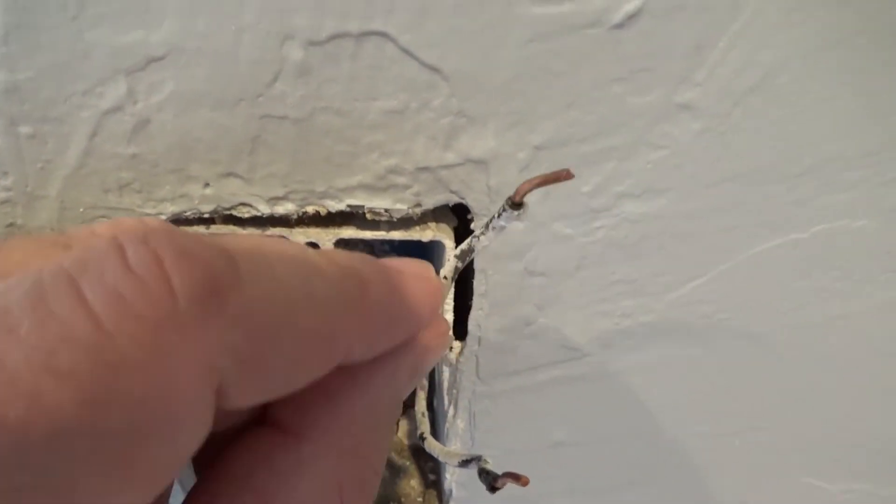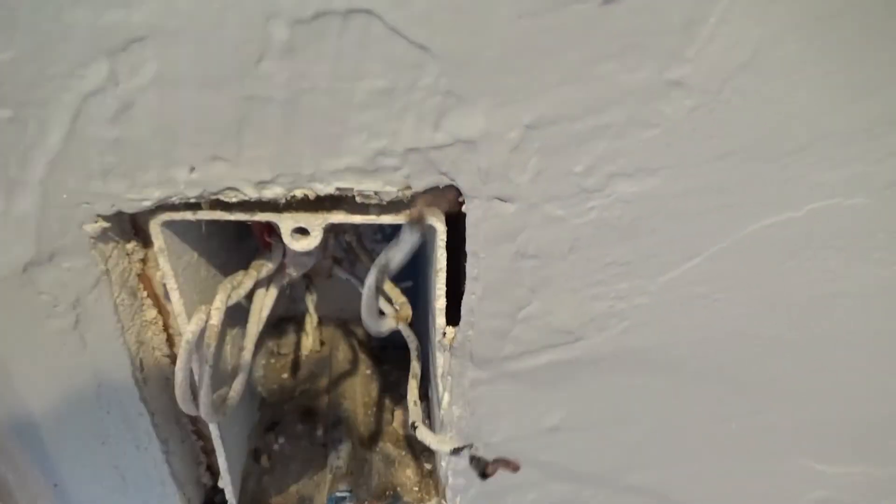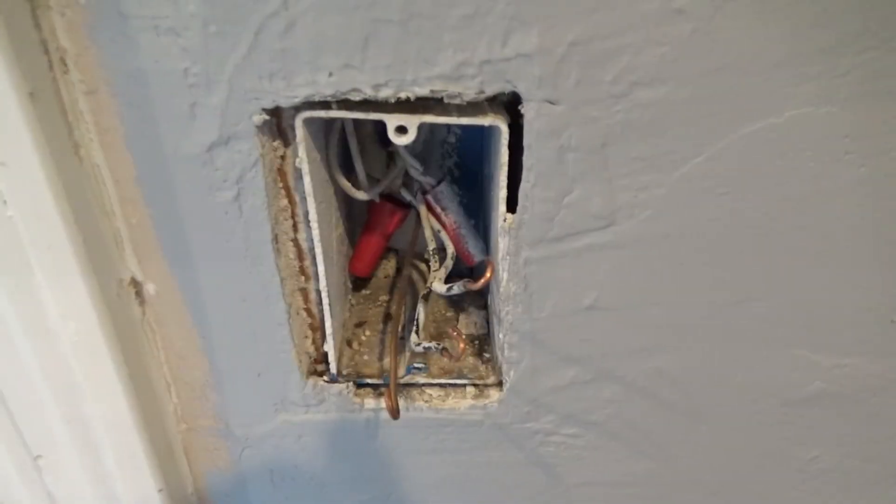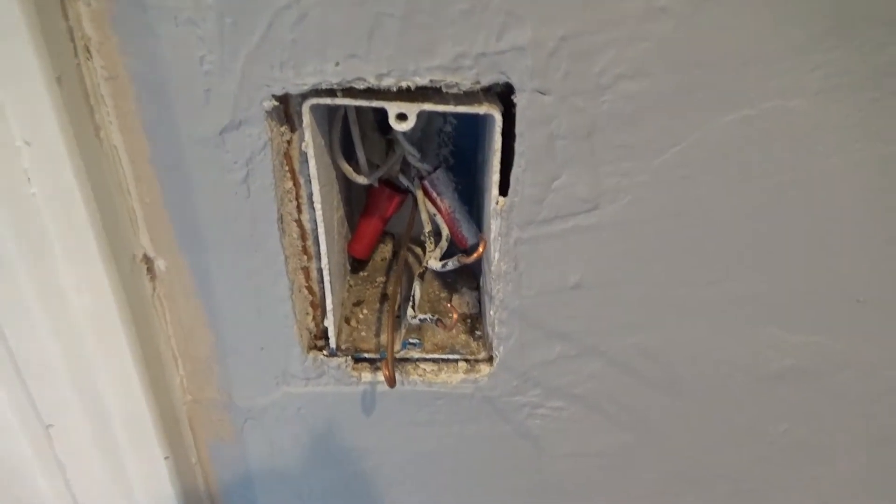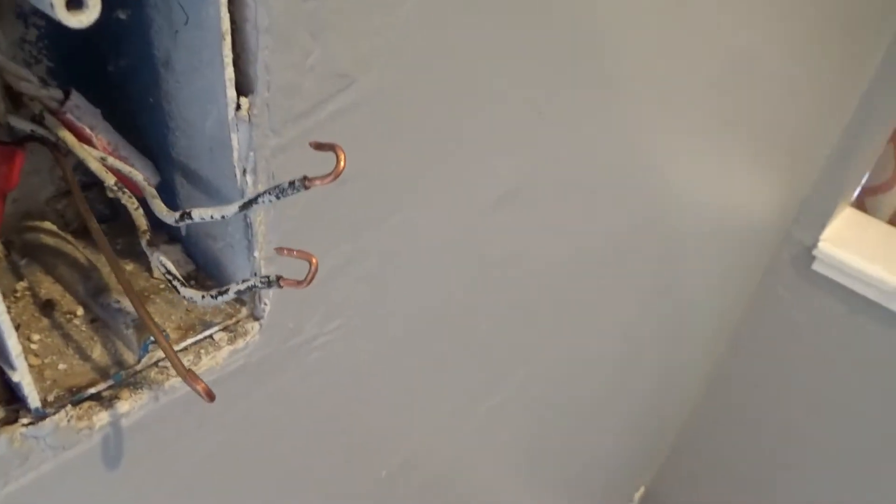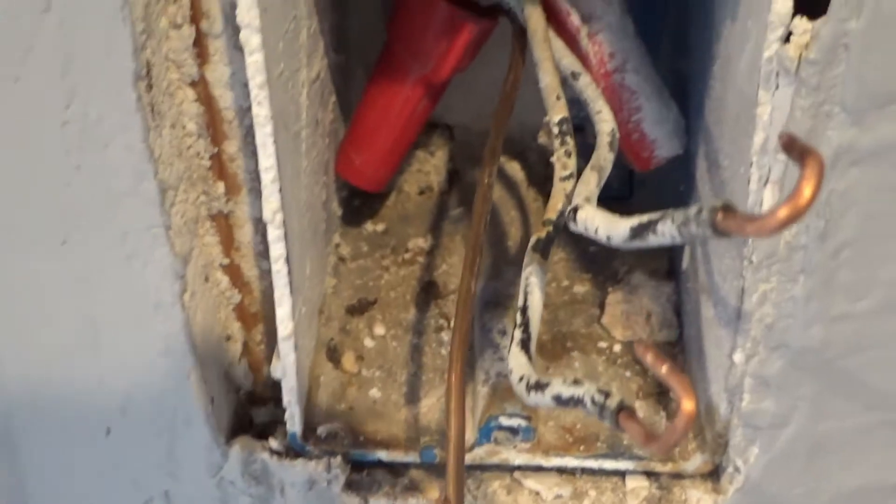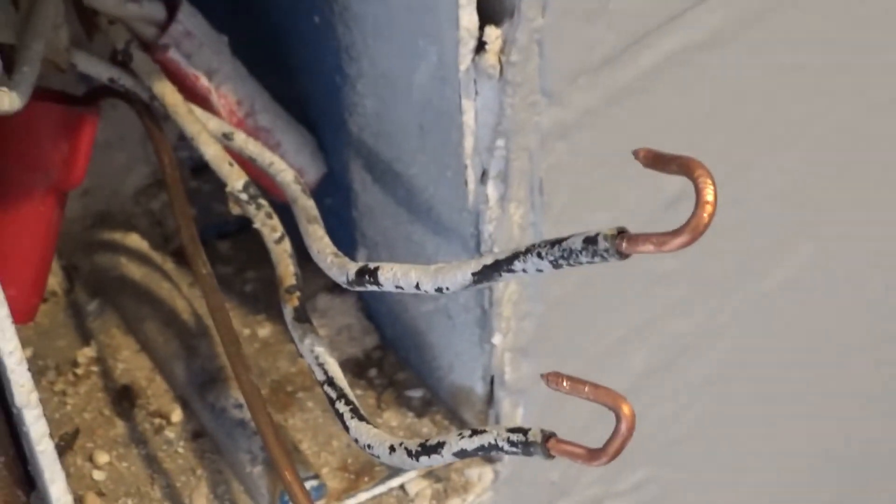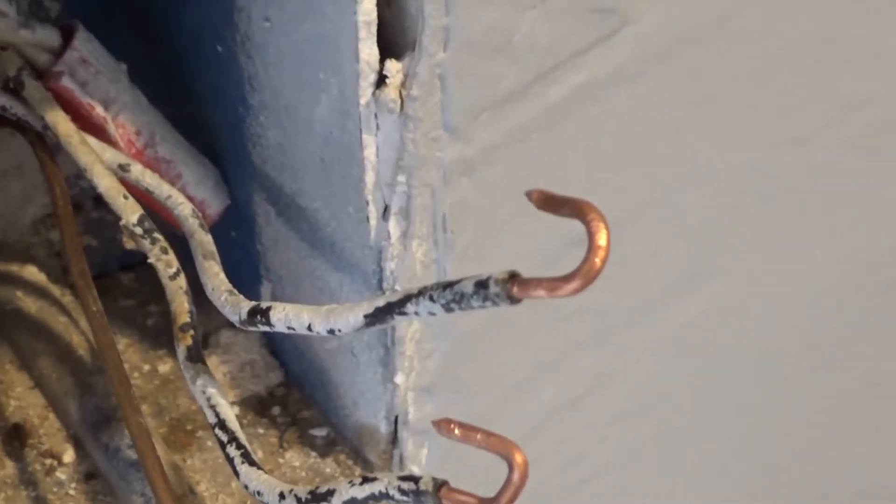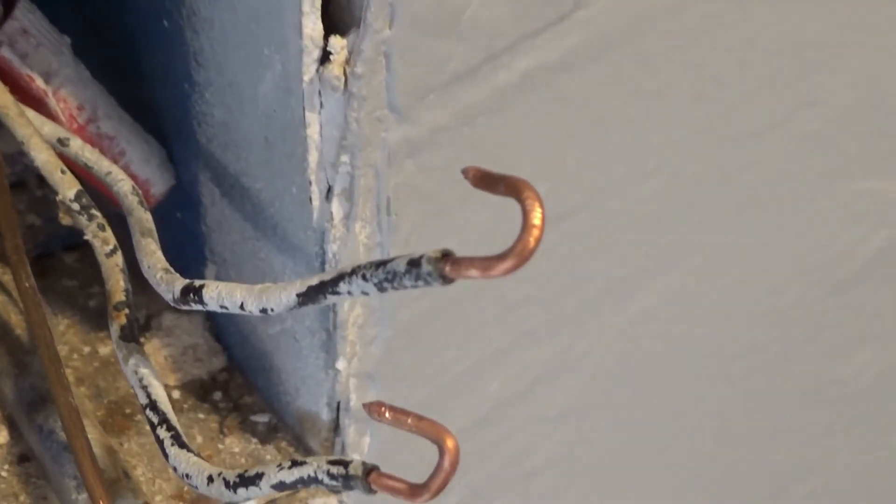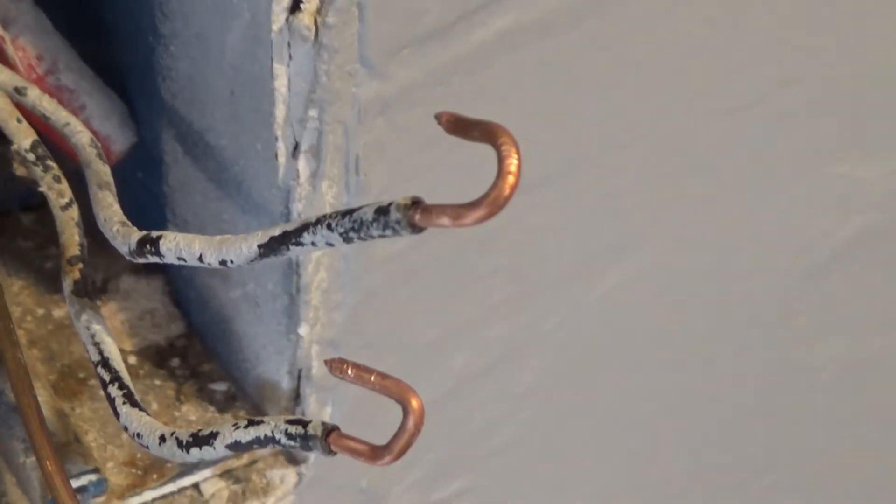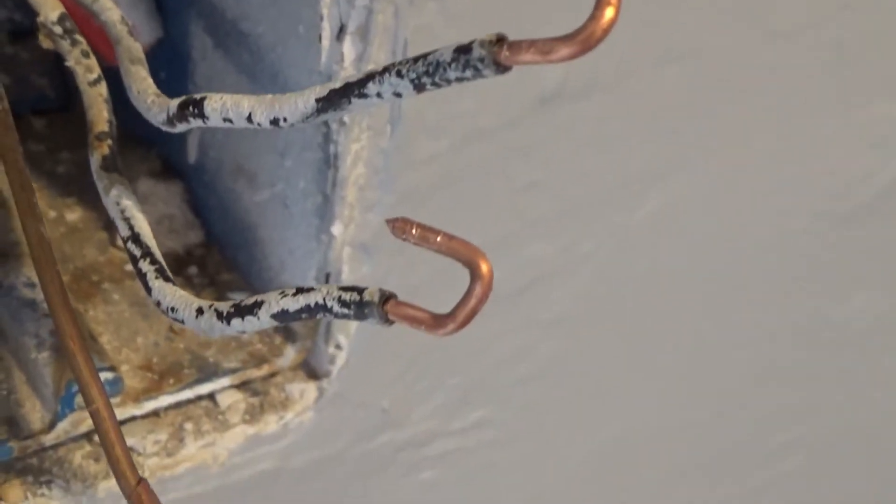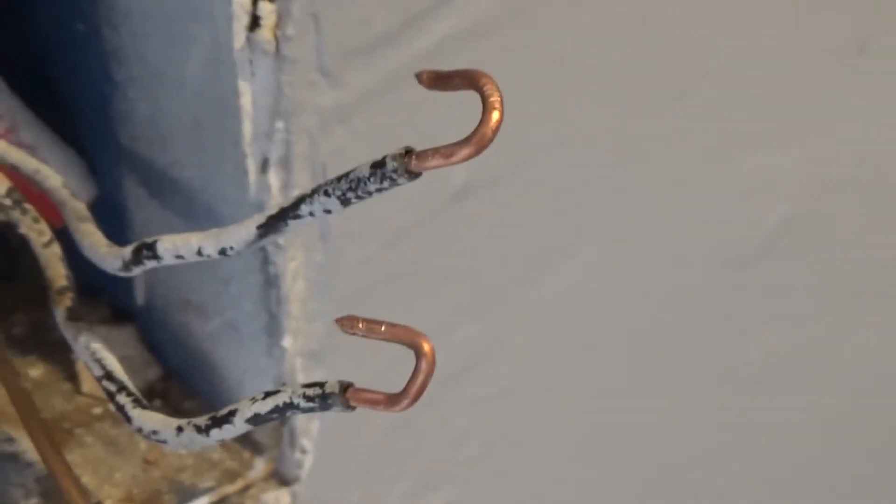What we did while we were gone is we put an extension or a pigtail on the ground because we just didn't have enough wire to work with. And we straightened up the copper that was there on the switch leg and the common, and we went ahead and re-looped it.